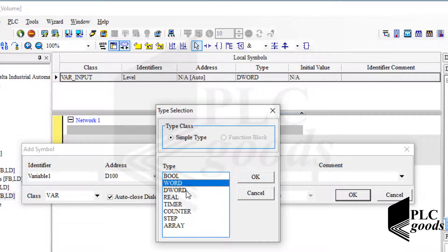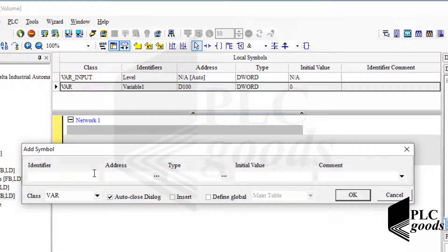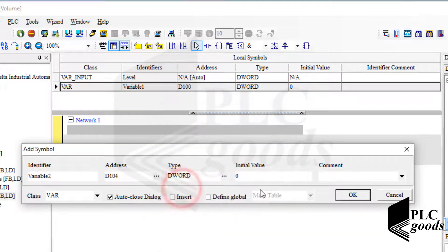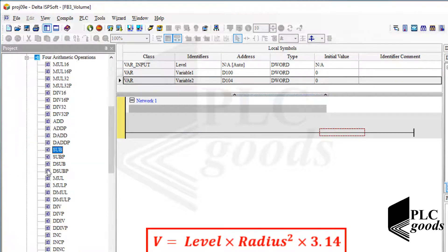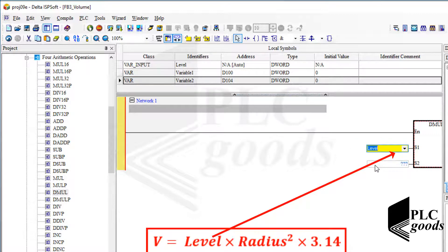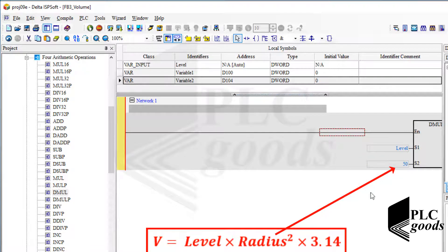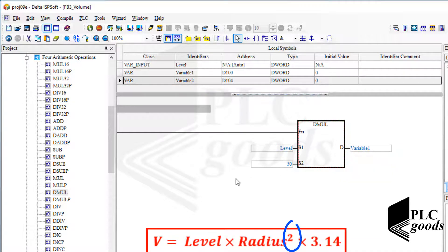Let me select double word — I usually prefer to do my calculations based on 32 bits. Therefore this symbol will use D100 and the next address D101. Now let's calculate the water volume based on this formula. I need some DMUL instructions. For the first input, let's use the level symbol; for the second one, assume the tank radius is 50 centimeters. I save the result on the first intermediate variable and multiply it by 50 again.